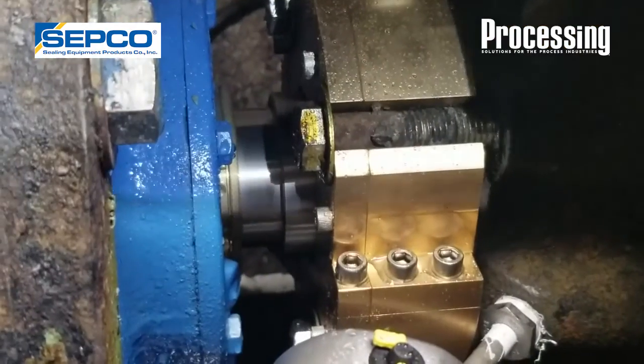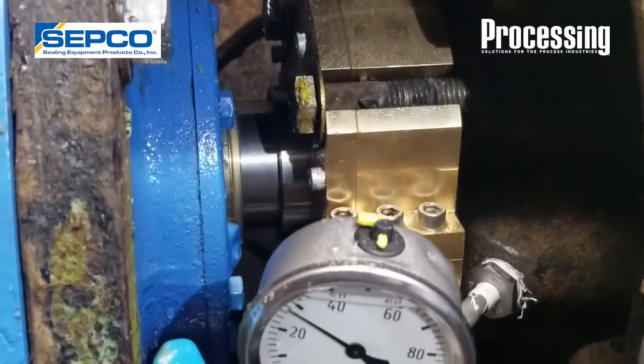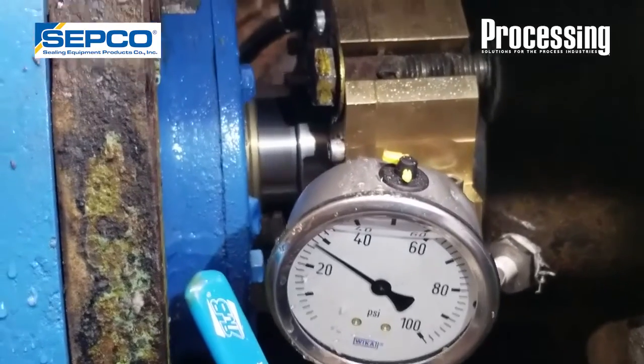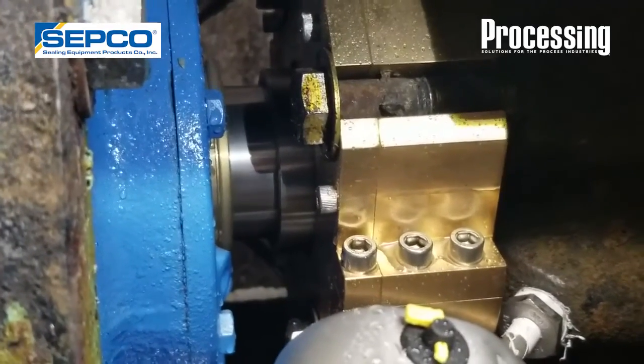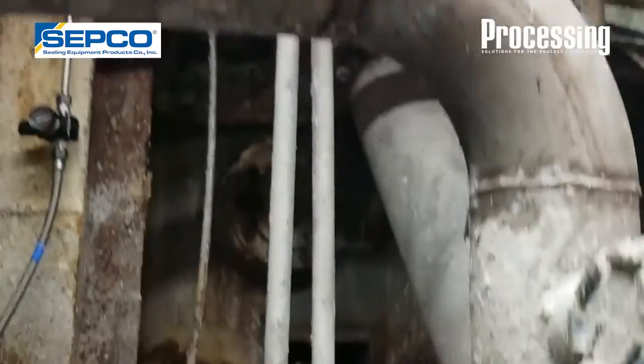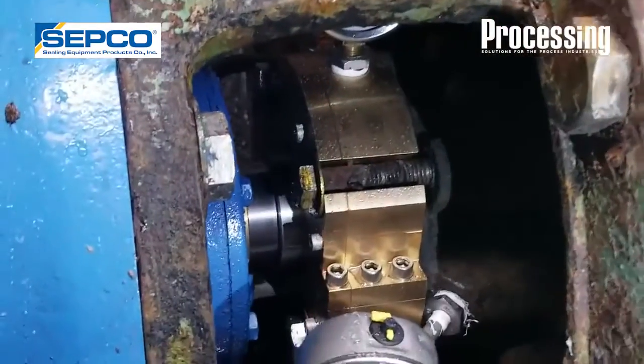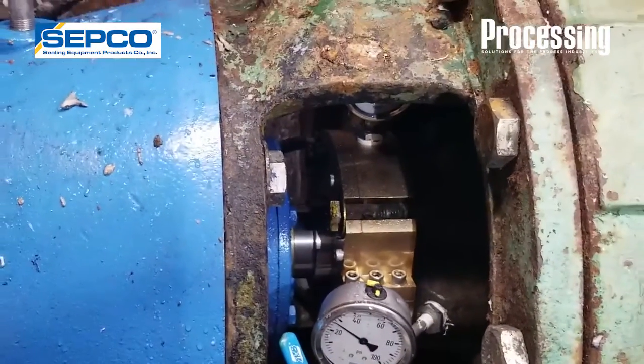So they had that issue with this pump, and we put on our SAS-P, and we introduced the hydroload to the stuffing box like I showed you before. That did 2 things. It throttles the air back, but it also stabilizes the shaft. And then to boot, we had the SAS, which can take 1/4 of an inch of runout, and we were able to seal that. That was over 18 months ago, and we are still going leak free. Because of COVID, we haven't been able to further this project along, just because gaining access to the plant's sort of tough.